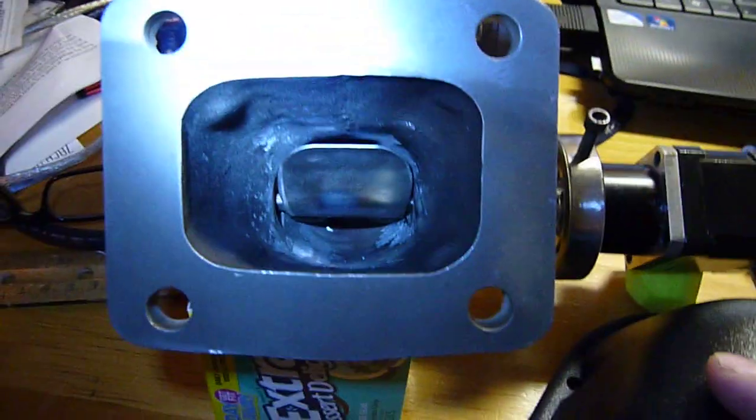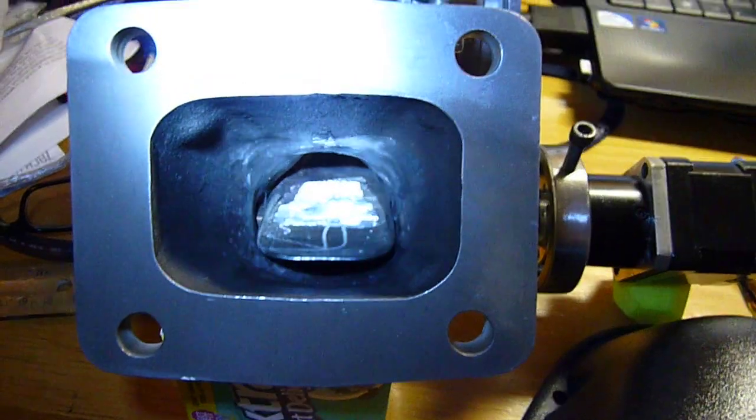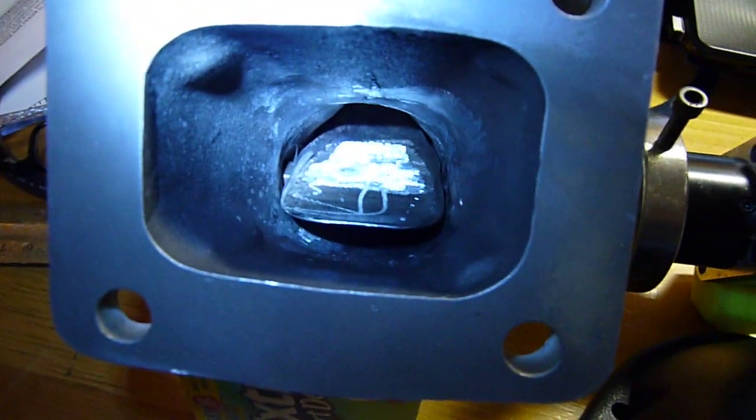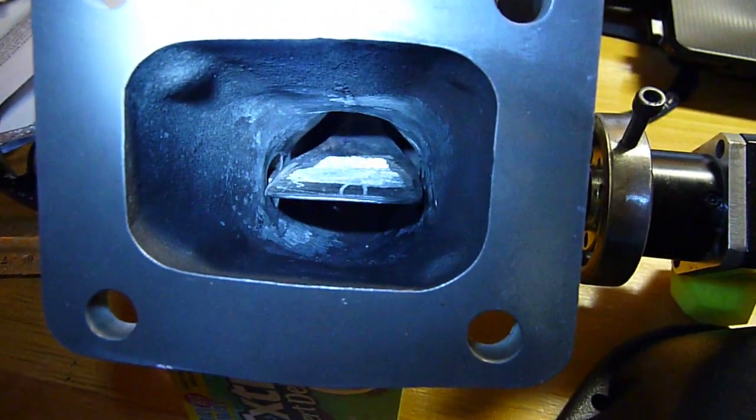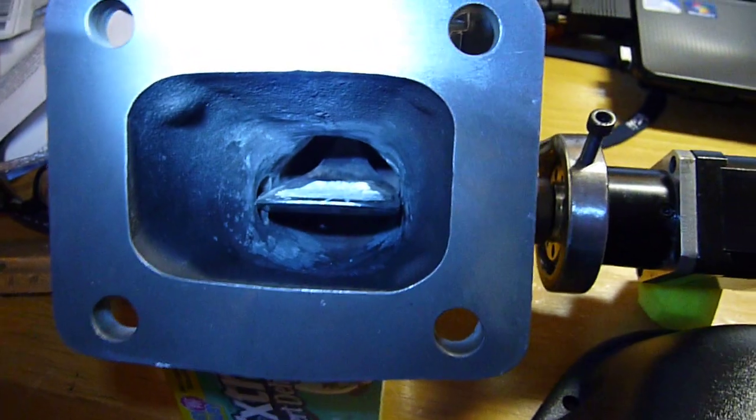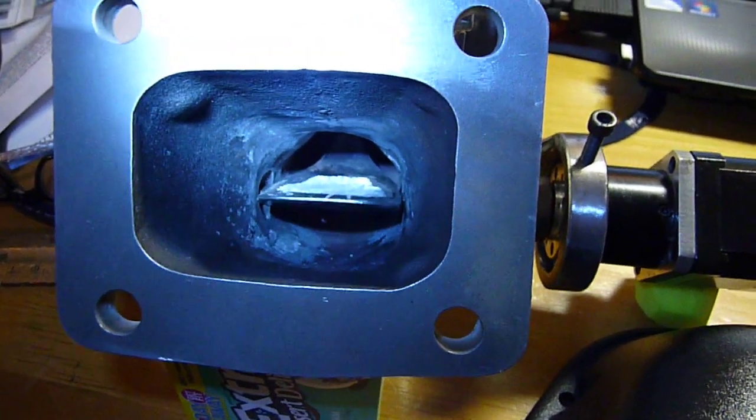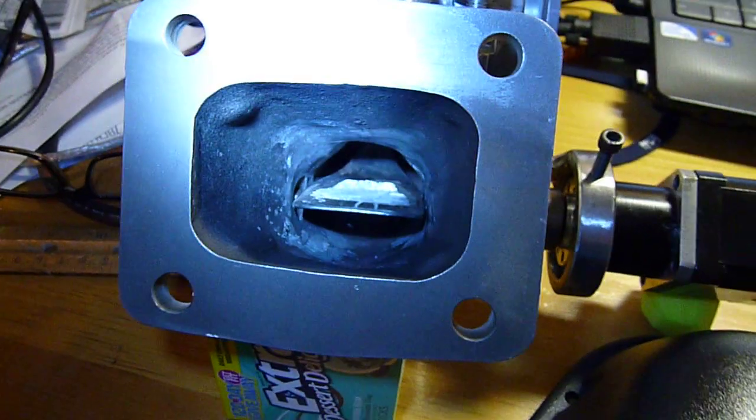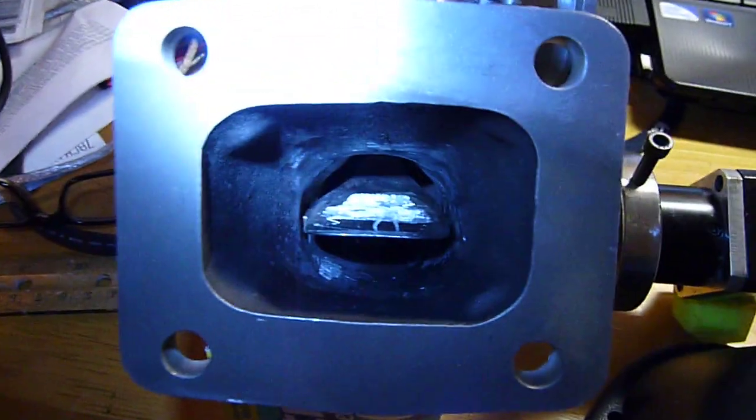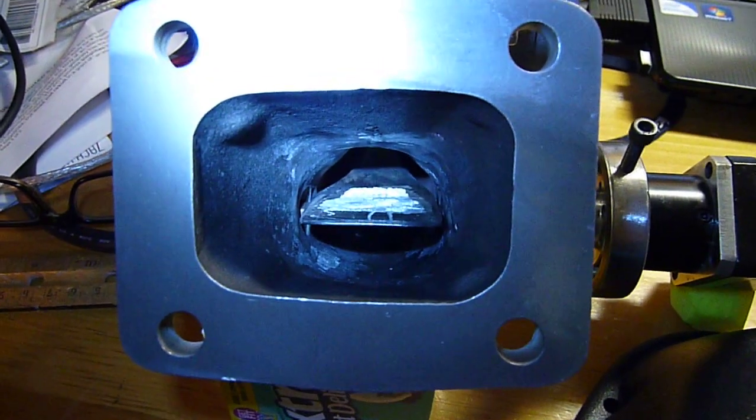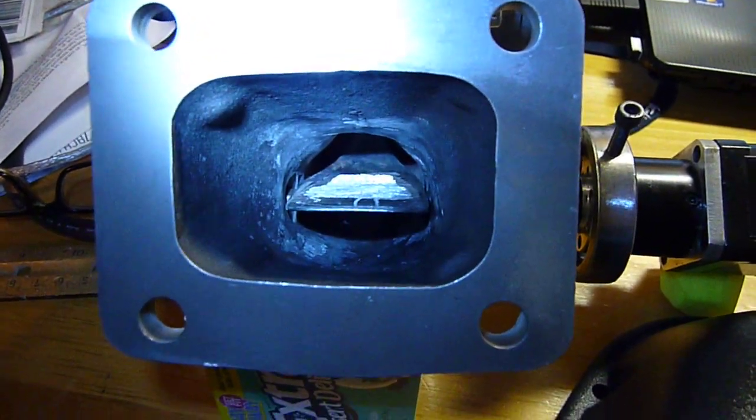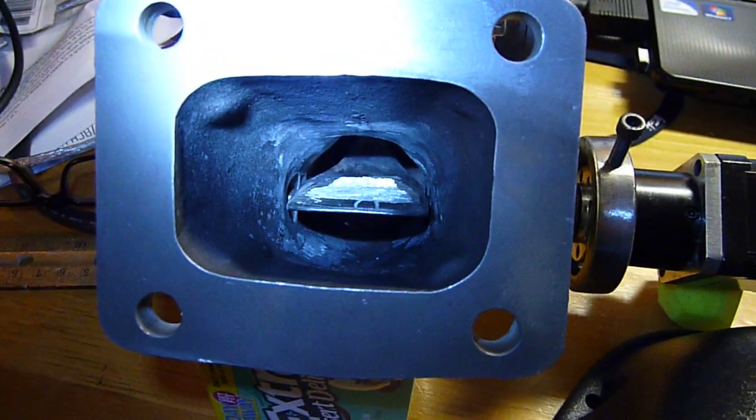But if you hit the engine brake again, it's going to go back to whatever position is determined by the inputs. So the nice part about this is that whenever the engine brake is released, it's going to go to the position that suits the flow and the shaft speed of this turbocharger. So basically you can come out of the engine brake and be right ready to accelerate again or whatever you're doing based on the sensor inputs.